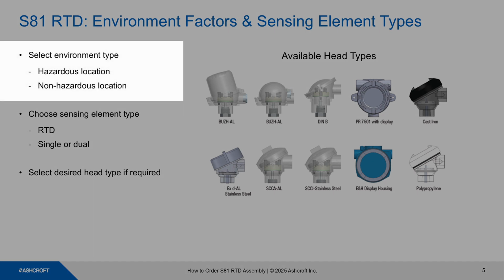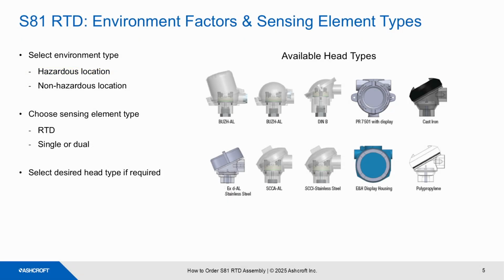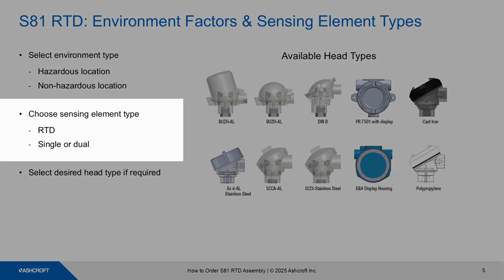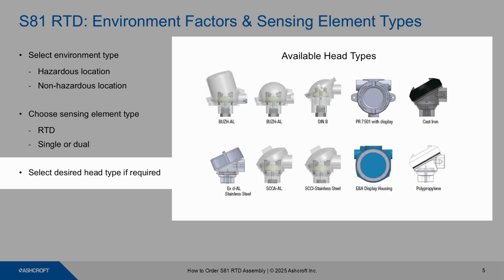Environmental factors will be based on the location of your application. It'll typically fall into one of two categories, hazardous or non-hazardous. A hazardous location is an area where there is a threat of a fire or explosion because there are flammable substances present. These locations are commonly found in oil and gas, chemical processing, pharmaceuticals, and mining. Once you know the location type, you'll be ready to select the sensing element, which can be a single or dual RTD. If a remote head is needed, you can select from the range of available head types that will perform best in your application.